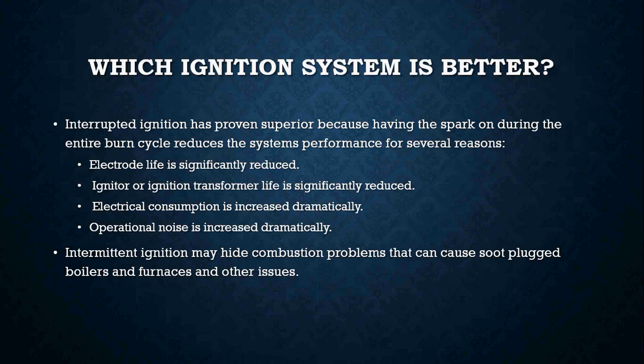The reason is that having the spark on all the time during the run cycle reduces system performance. It puts a lot of wear and tear on the parts in the oil burner, especially the electrodes, whose life expectancy is reduced. The igniter and ignition transformer are used a lot more than they need to be, so their life is also reduced. You're going to use a lot more electricity to keep the burner running, and it could be a little more noisy because the spark is on all the time.